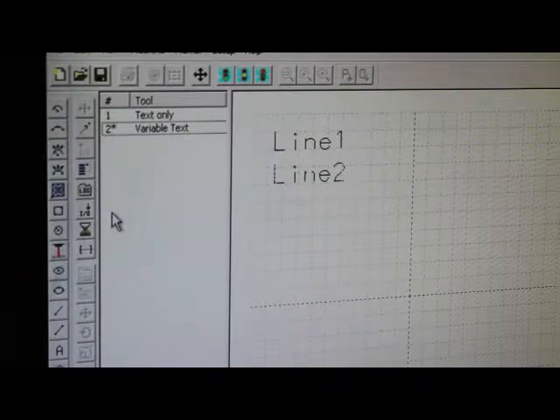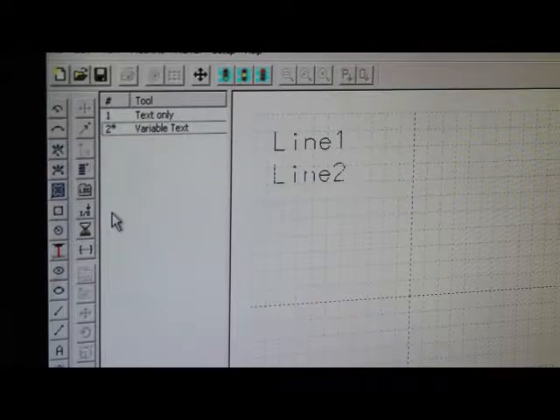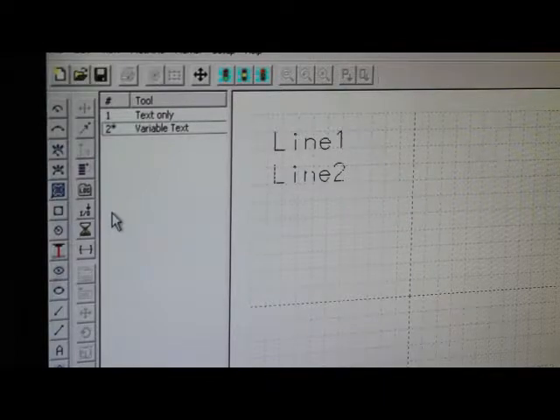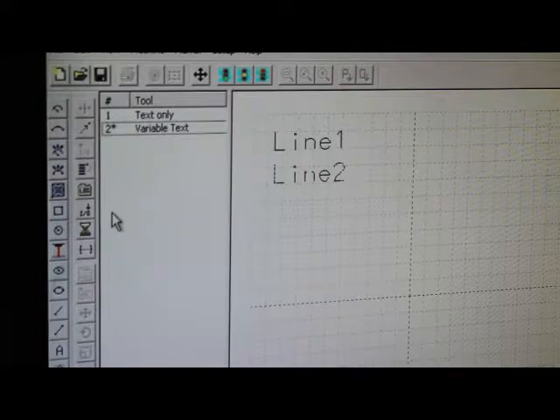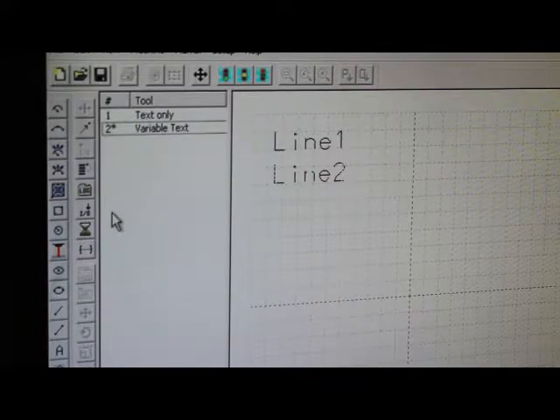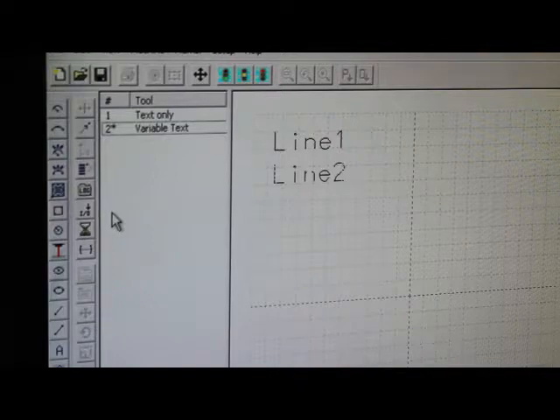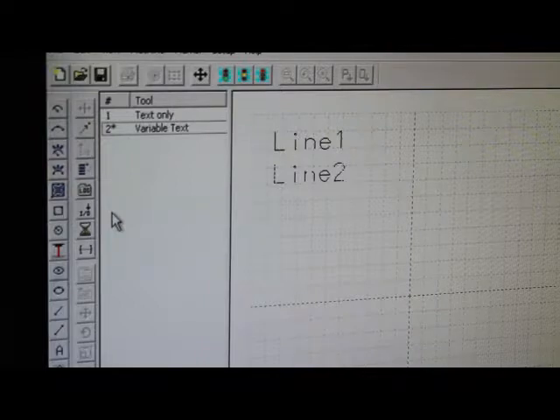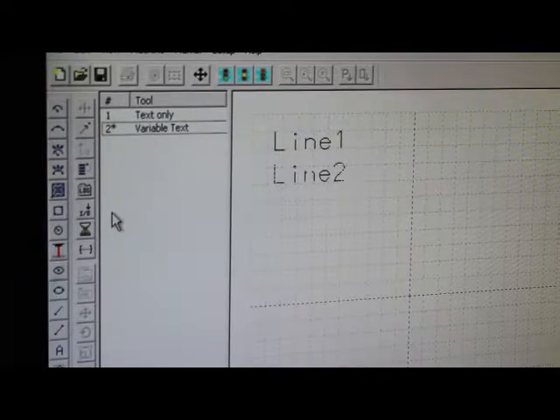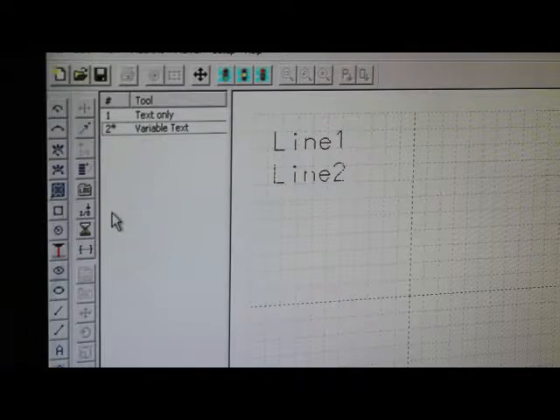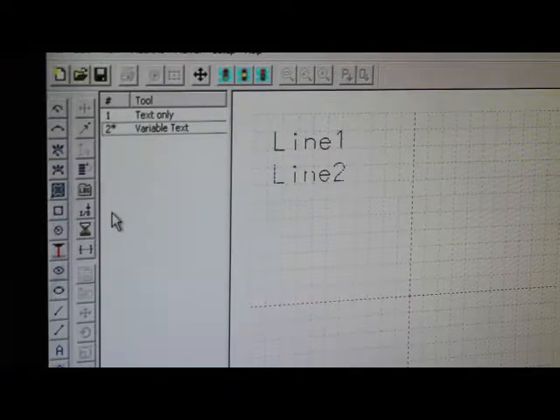And there's a lot of different message types. One is text, V is variable, and we saw P is pattern. Then it will send a start of text character, which tells the receiving unit that the text or data is the next thing that's going to come. And that would be the line number and whatever the data is. And then it follows that with an end of text character that says this is the end of the data, and a carriage return that basically says this is the end of the message.